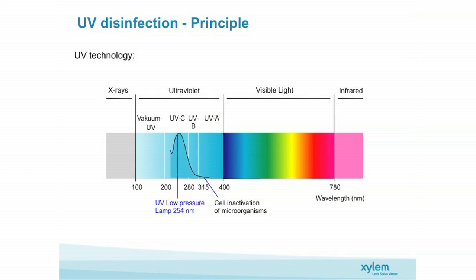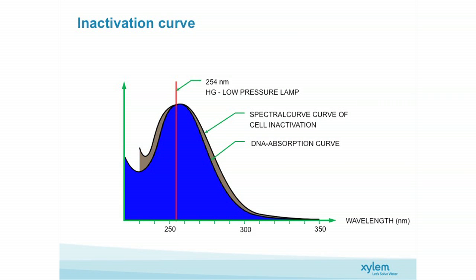The other technology in Wedeco's arsenal of disinfection then is UV. Okay, I'm still not convinced on UV, but my colleagues will convert me slowly, I suppose. UV is using the energy of light to create a chemical reaction within a cell. You're actually breaking down the DNA of the cell with UV light sitting at the 250 nanometer level. UV light is the light spectrum just above visible, from 400 nanometers down to about 100 nanometers. The one we're interested in is the UVC band at 254, which is the highest absorption rate of DNA within the cell. So you end up with a high absorption rate at that point.